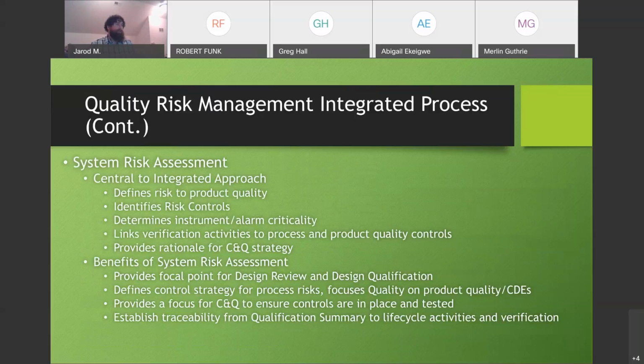So system risk assessment is central to the integrated approach, defining the risk to the product quality, identifying the control measures, the risk controls, what is the instrument and alarm criticality, and it really links the verification activities to the process and product quality controls, and provides rationale for the commissioning and qualification strategy.